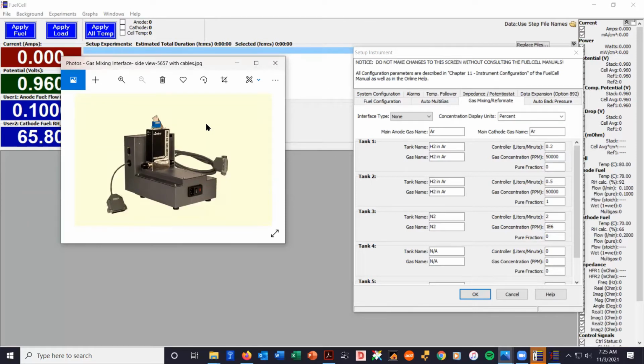An example here would be a corrosive gas, maybe like a NOx or a SOx, sulfur dioxide, something like that, or H2S, or another common one would be carbon monoxide. Sometimes people do testing with carbon monoxide, and that tends to adsorb onto the surfaces of the humidifier and all the tubing.